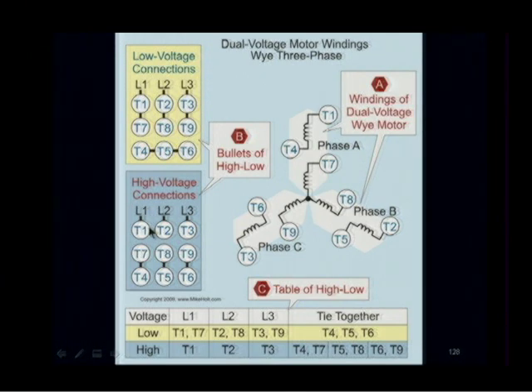High voltage connections: 1, 2, 3, and then tie 4 and 7 together, 5 and 8 together, 6 and 9 together. So T1, T2, T3. Now I know where the T comes from, why it's T1, T2, and T3. Terminals. And then you have 7 and 4, and 8 and 5, and 9 and 6 tied together, and that's how you connect to different voltages.